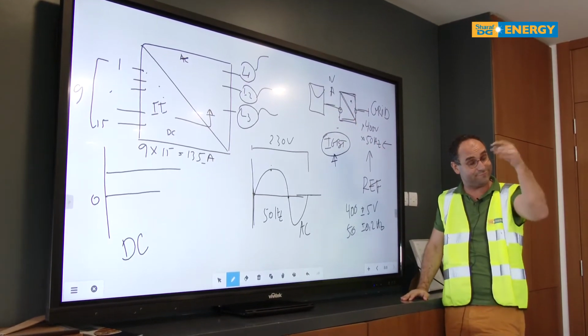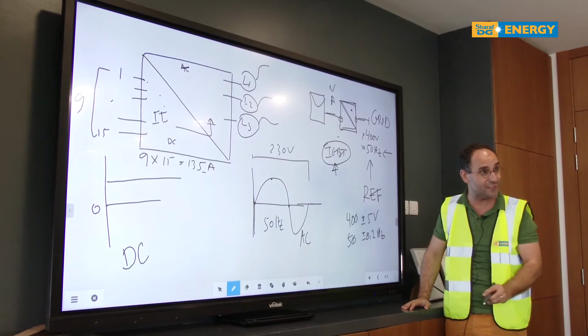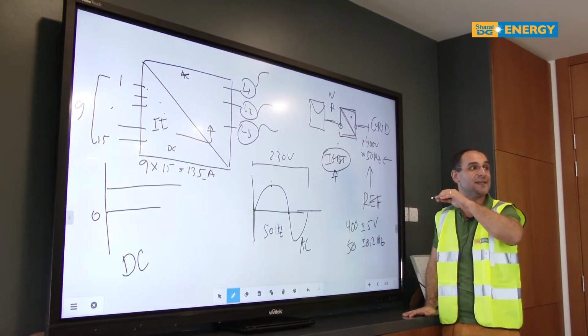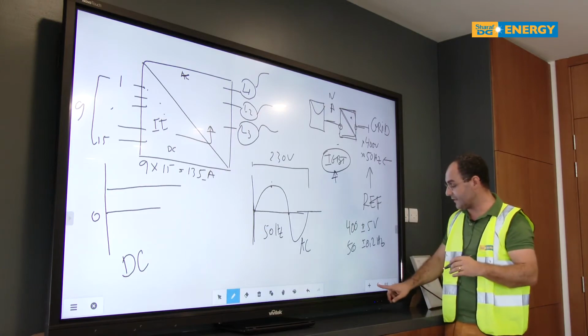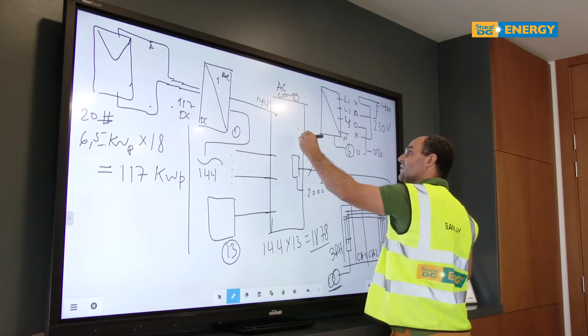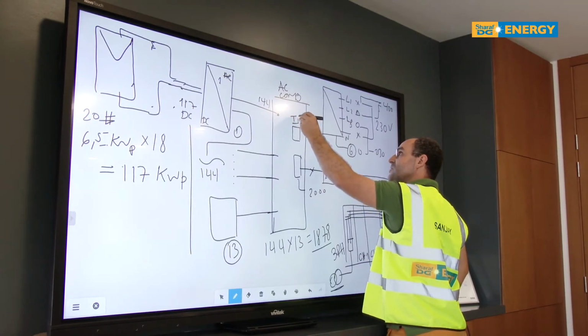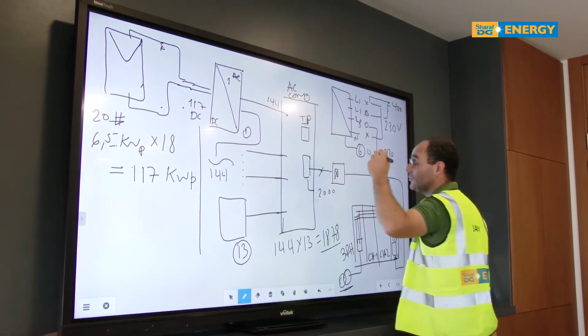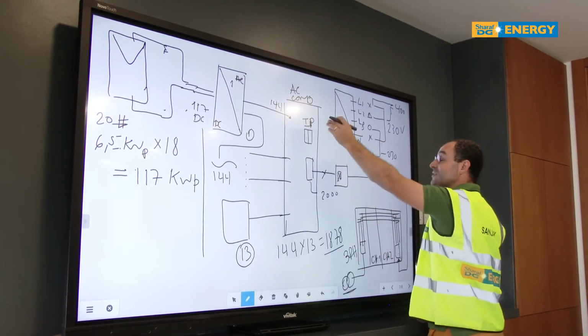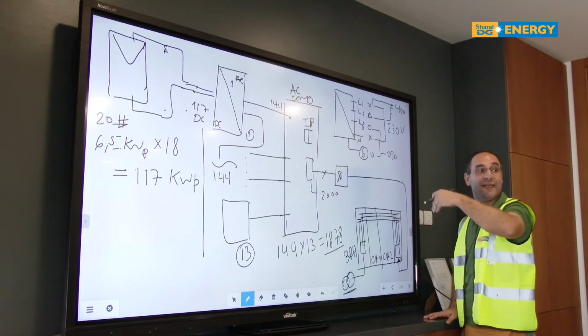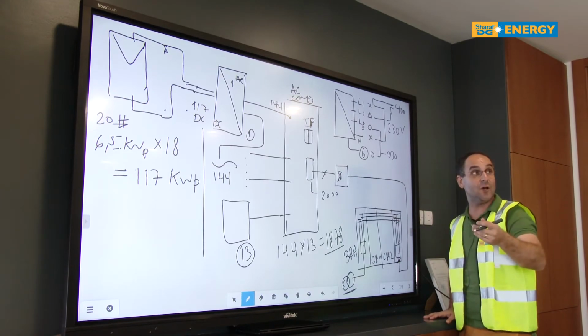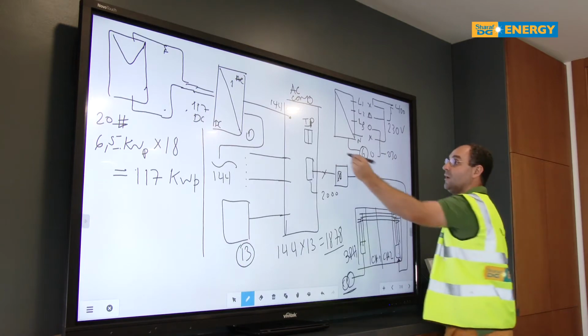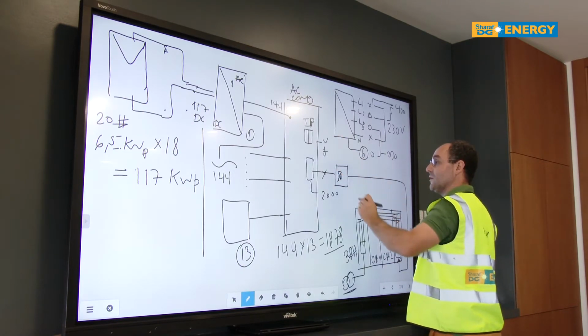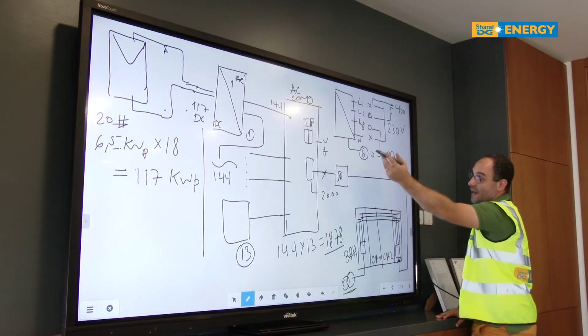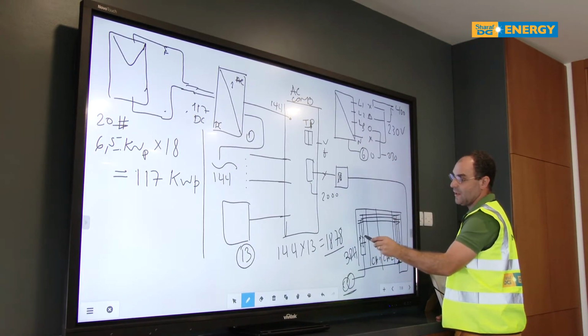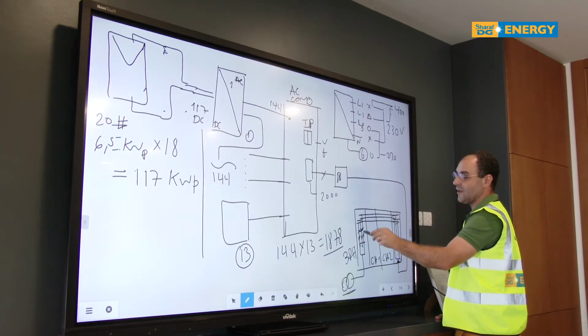But DEWA, when the consultants wrote the regulations of DEWA, they had another IGBT as a redundant feature, and that comes here. People usually call it interface protection. We will see this running later, not today. What is the concept of this machine? It is to replicate the IGBT feature, but on voltage and frequency. So this guy is sensing the voltage in each line and the frequency on each line on the DEWA side.